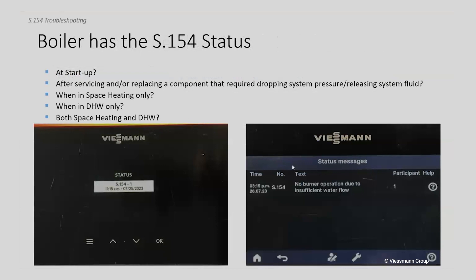The S154 scenarios — what do we have to look at at startup commissioning? I've spent a few Friday afternoons with stressed-out contractors with S154 on the screen after they finished commissioning a boiler, trying to figure out why the boiler is not firing up when it should be. We're going to look at that scenario fairly intently. After servicing or replacing a component that required you to drop the system pressure, anytime we're adding air into the hydronic system we need to remove it. The same procedure used in commissioning startup would be the same thing I'd recommend if you're having trouble with S154 after extensive component replacement.